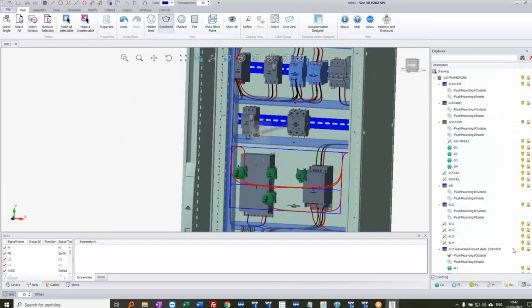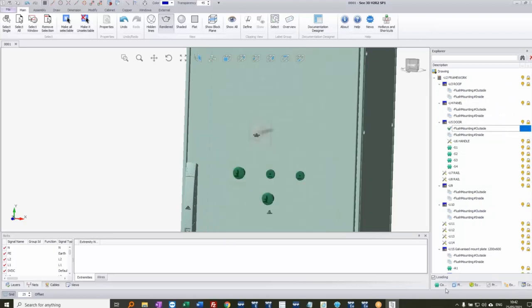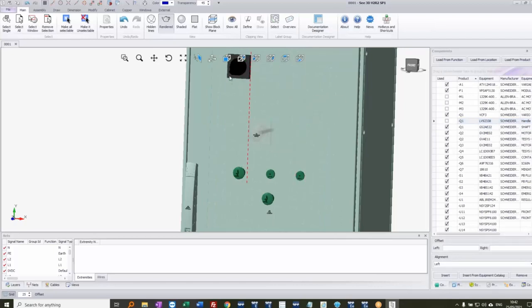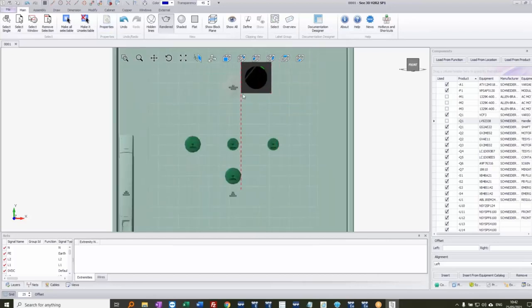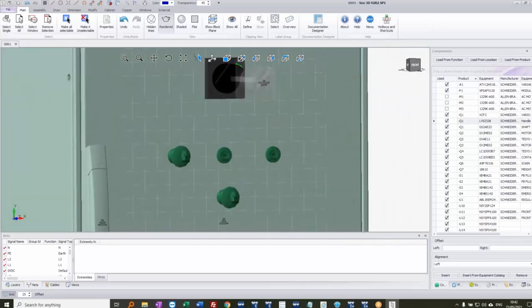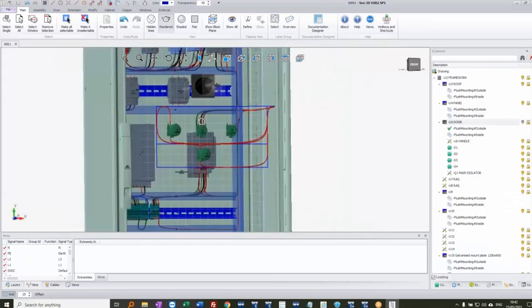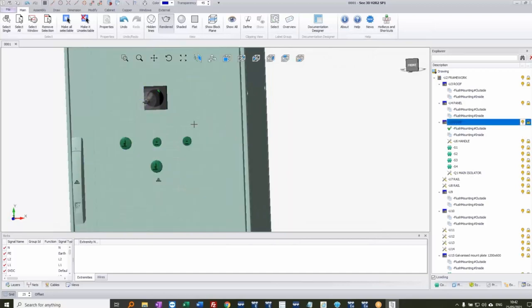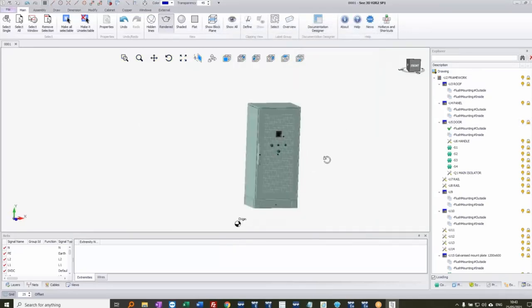I need the handle to appear on the door, so I go back into Explorer, turn on door display, and set mounting on the outside surface. With object snapping on, I move over the position of the disconnect switch and it snaps exactly into position, aligned straight through to the door. Turning off the door confirms it's in exactly the right place. It's attached to the door, so when I create a drill template it knows exactly where the hole should be.